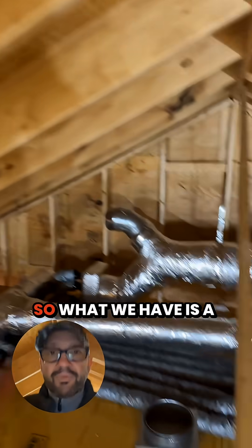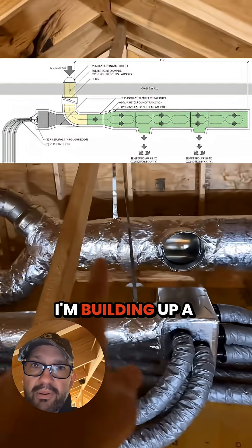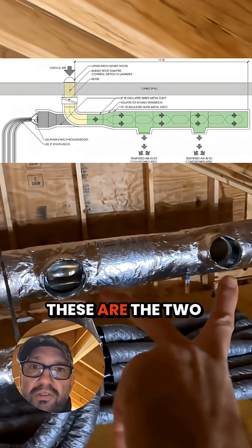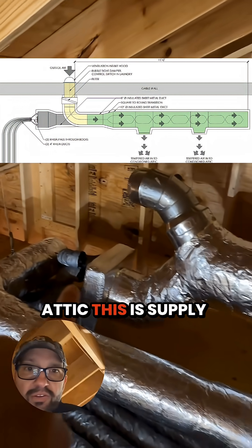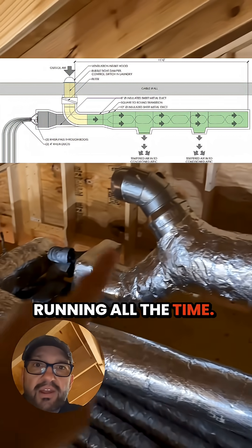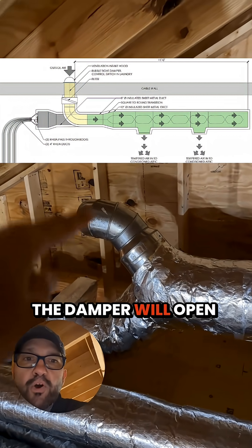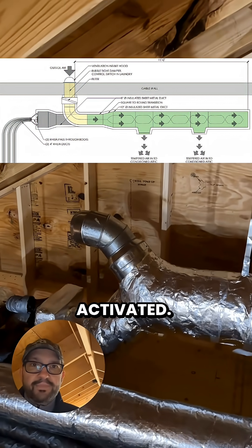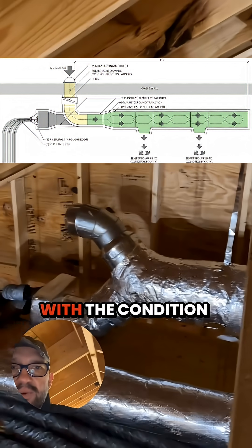We're mixing all that in here before it enters the return side of the air handler, is filtered, conditioned and then redistributed. So what we have is a 12-inch duct, and it's a chamber — I'm building up a mixing chamber here. These are the two outlets that dump the air into the attic. This is supply air; this will be running all the time. There'll be a damper and a filter here, and the damper will open up when the dryer is activated. It'll dump this outside air into here, start mixing with the conditioned air.